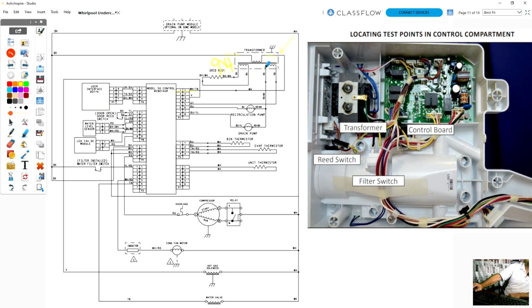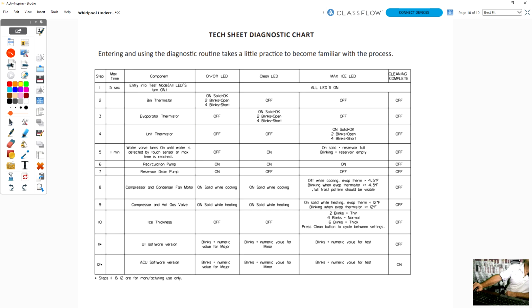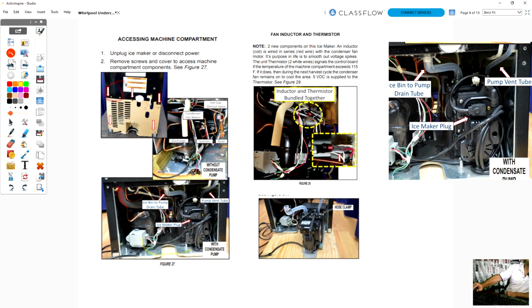Now this voltage here is voltage that is going to the board, but look how the circulation pump and the drain pump run back to this output here. So that voltage coming off of the board here goes into the gray here, and then there's some relays that's sending that voltage out to your pumps. Since your pumps are not connected to line 1 and neutral, those two pumps are not 120 volt pumps. Those are low voltage pumps.